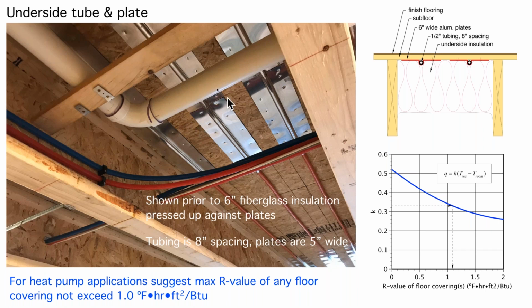A couple other things: keep the drainage piping and your water piping below the insulation, especially traps. We don't want to put traps up under a heated floor and have insulation underneath them. What'll happen over time, if that fixture isn't used a lot, is it'll actually dry up the trap and you'll get some sewer gas coming up through there. And the other thing, especially with cold water lines, you don't want the cold water lines running above that insulation because that will heat the cold water. And if you're looking for a cold glass of water and the heating system is on, obviously that isn't good. So small details like that are important.